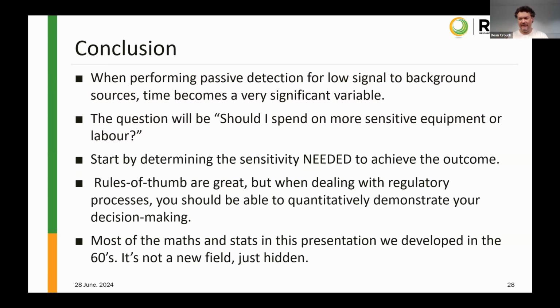And if you've got a point of reference that hasn't changed, you can go back with meters and verify the response. You've got 17 counts per second, but now with this new unit, it's 25 or something. That's the only one I can do.